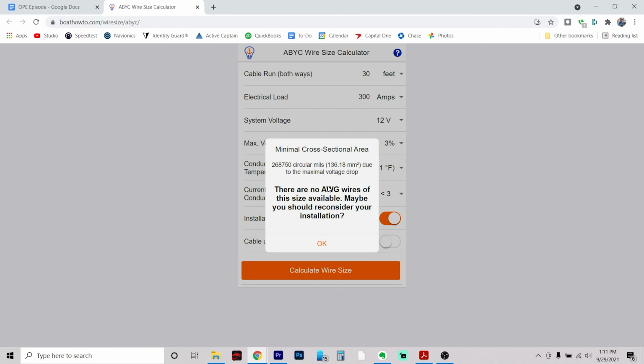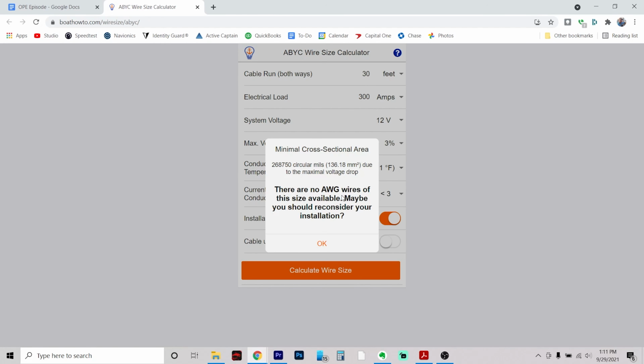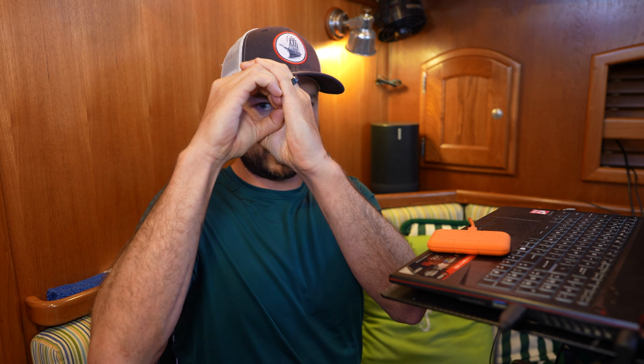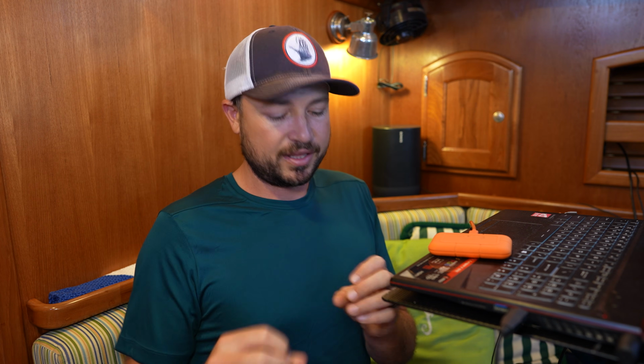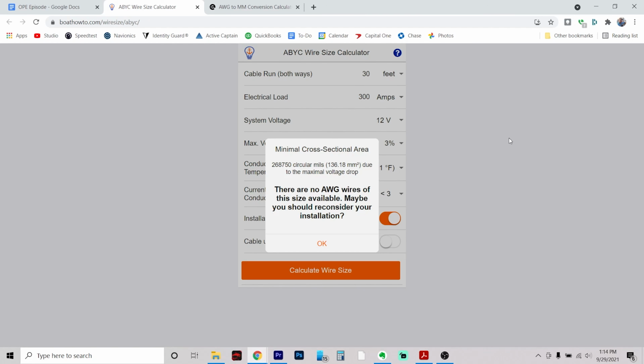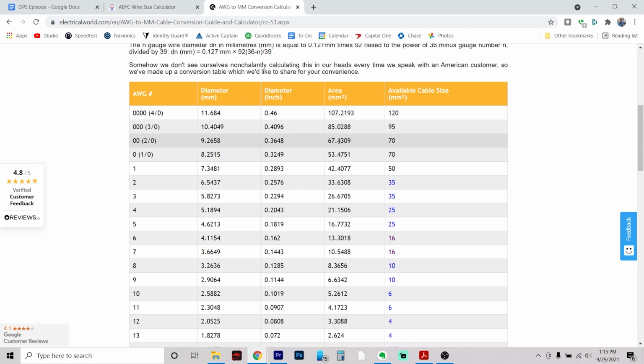So I hit calculate and boom, it says there are no gauge wires available. The largest gauge wire that we can get is 4/0 cable, and even that won't handle this load over that distance. But if we look up here, we can see we need 136 square millimeters. That's the cross section of the cable. That's like this. So we know that we're gonna need 2 cables that if we add up their cross-sectional area, it will equal 136 square millimeters or greater. We could potentially get away with 2 2-aught cables, but that's just under the 136 square millimeters that we need, so we decided to go with 2 3-aught cables.